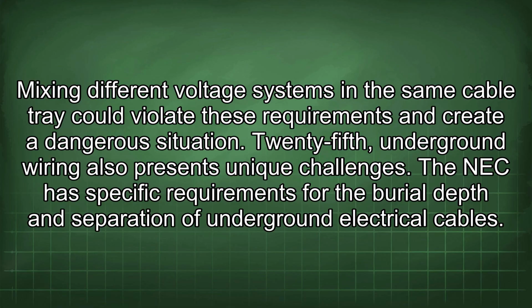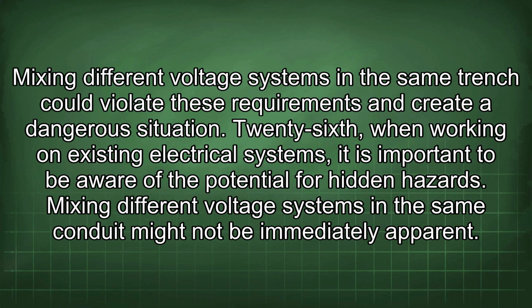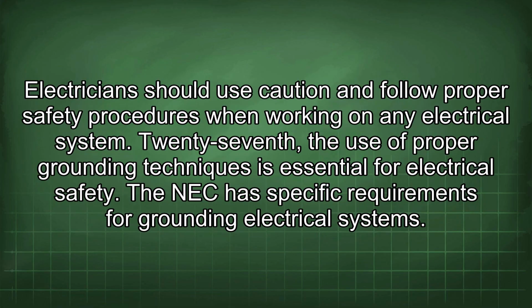25th, underground wiring also presents unique challenges. The NEC has specific requirements for the burial depth and separation of underground electrical cables. Mixing different voltage systems in the same trench could violate these requirements and create a dangerous situation. 26th, when working on existing electrical systems, it is important to be aware of the potential for hidden hazards. Mixing different voltage systems in the same conduit might not be immediately apparent. Electricians should use caution and follow proper safety procedures when working on any electrical system.